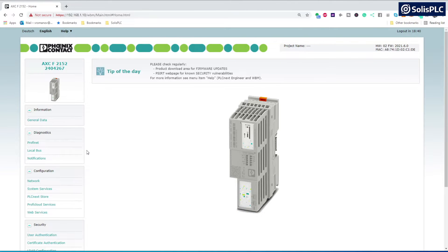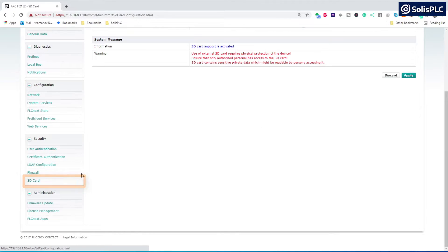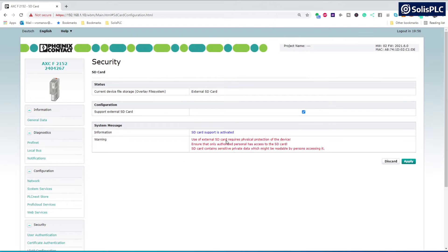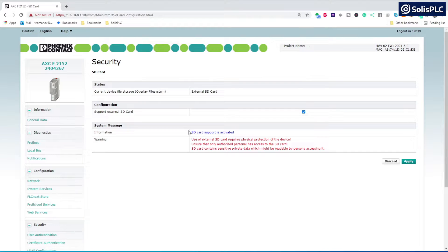The first item on our list is managing the SD card. As we can see in the WBM, there's a section called SD card. We need to navigate to this section and make sure that the external SD card is enabled. The Docker installation is going to require the space of an external SD card, so make sure to purchase a 2GB or larger SD card for your PLCnext before proceeding, and make sure that it is activated.